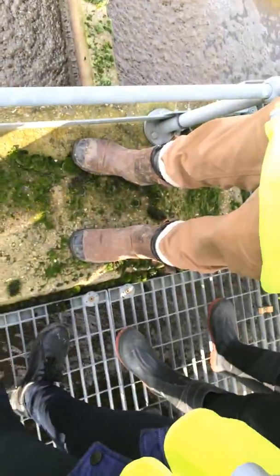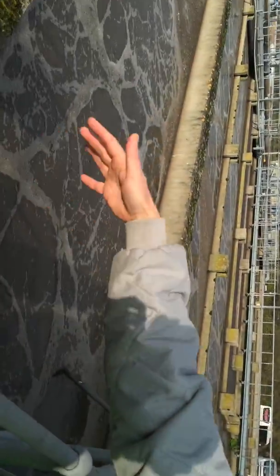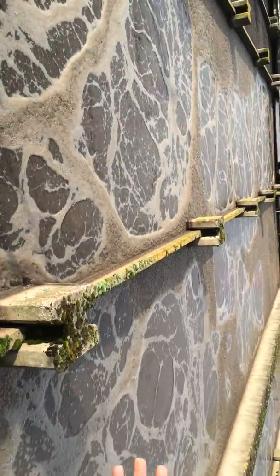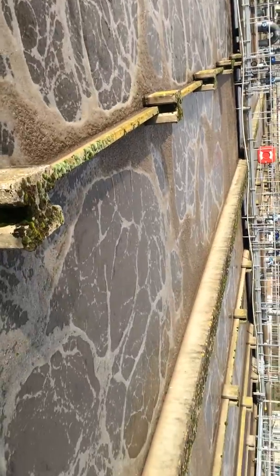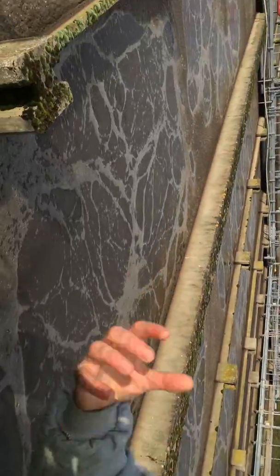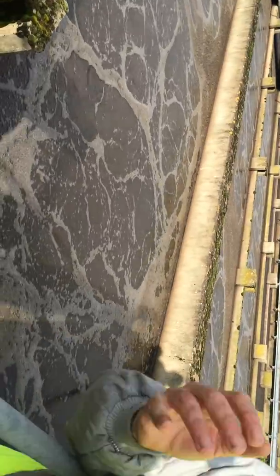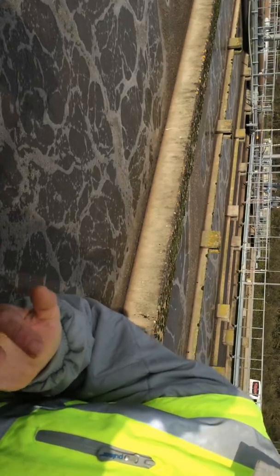So the 6 lanes, but then the flow is all commoned up from those 6 lanes again, the mixed liquor. The solids concentration in these activated sludge plants, in this one, is probably about 4,000 milligrams per litre. So if you took a sample out of here, what you would see is a very rapidly settling biomass, about 4,000 milligrams per litre, which effectively is a biological population that we're using. They're the bacteria which are oxidising the carbonaceous BOD to carbon dioxide and water. They're oxidising the ammonia to nitrate in the aerobic zone, but what they're also doing is growing.